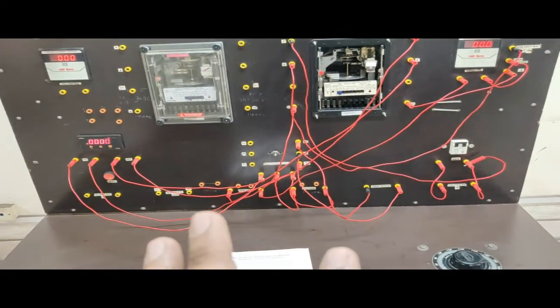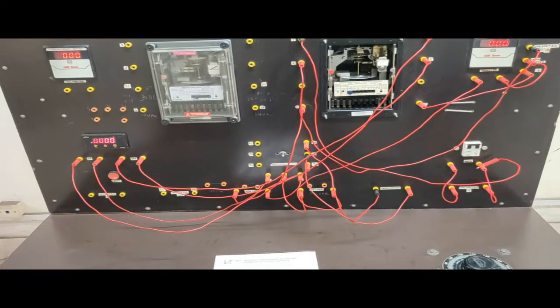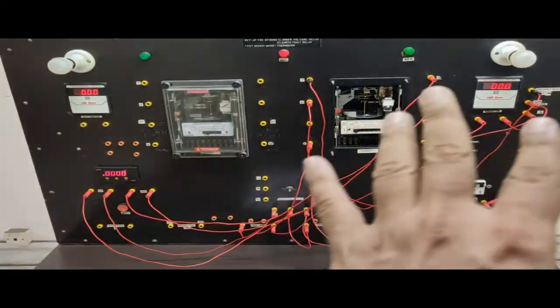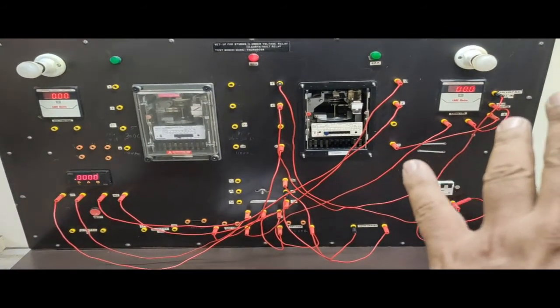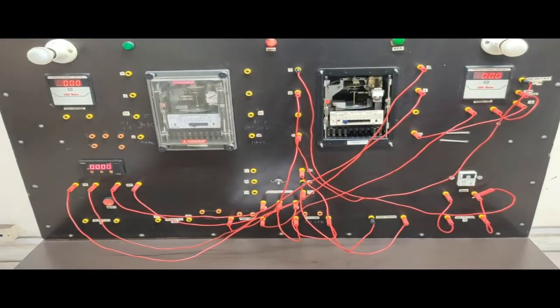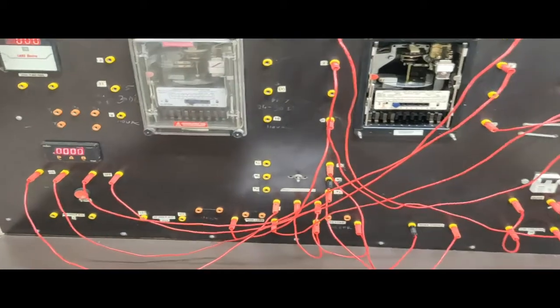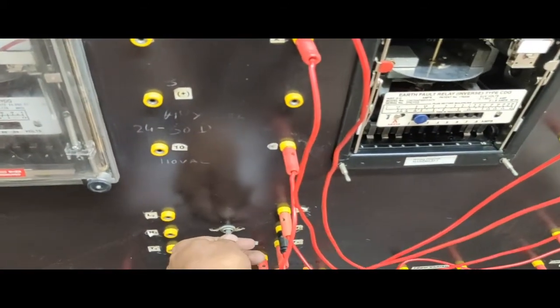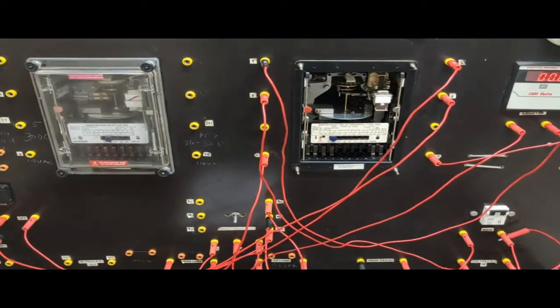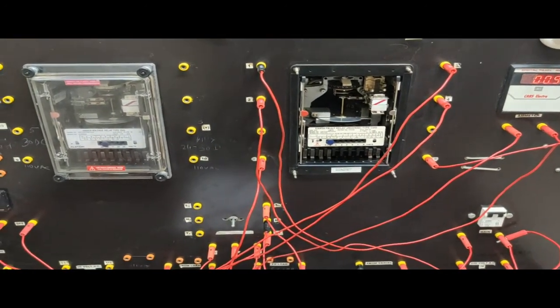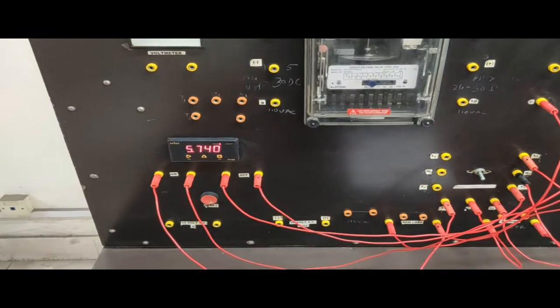condition. So in the pre-fault condition, here we actually know the fault current, because if I just put the selector switch in the downward position, we know that 0.8 ampere current will flow to the relay coil. This is our fault current. So this is a predefined fault. Now I just apply the fault to the relay and you see the relay starts moving and it will generate the trip signal. Let's see how much time is required.